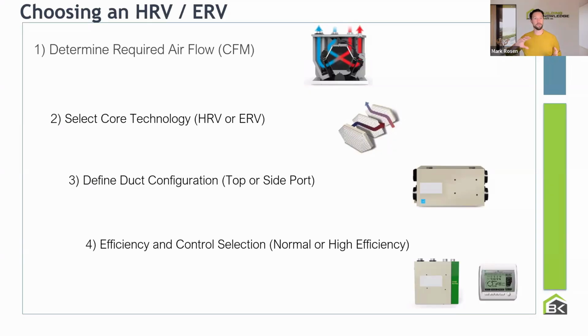And I will say this debate has evolved. When ERVs first came on the scene, HRVs were fairly well entrenched, and there was a debate: is ERV an upgrade or not? I would say that in most locations across Canada, except for perhaps the warmest climate zones like Vancouver, ERVs have sort of risen to the top. An ERV core has more benefits than detractors, and the ability to maintain humidity is always something we're interested in, whether we're air conditioning or heating in the winter. And so ERVs are very frequently the default choice nowadays.